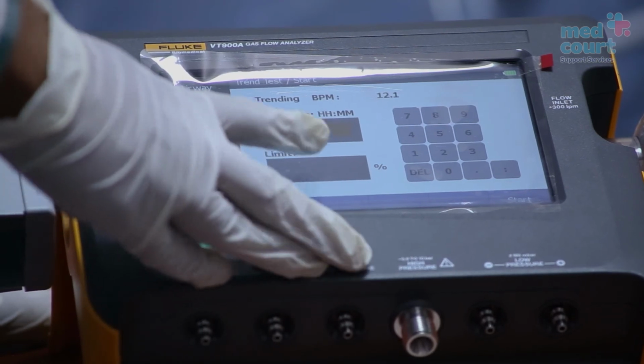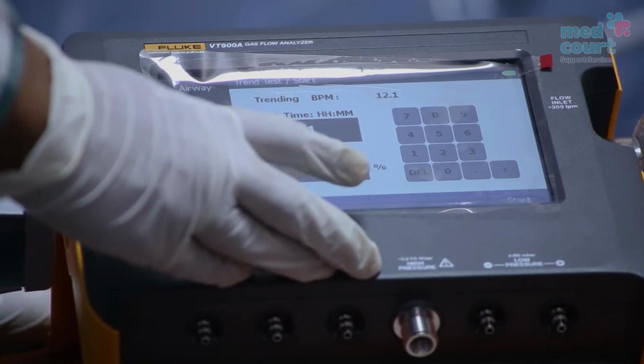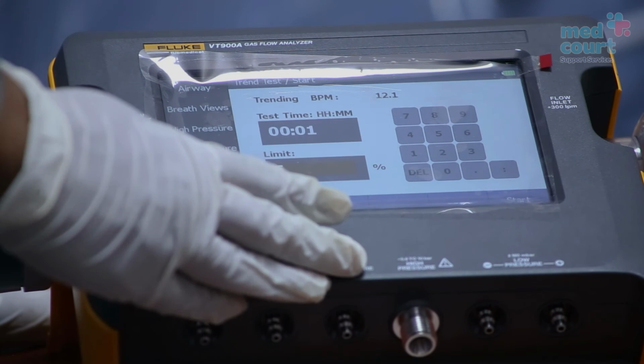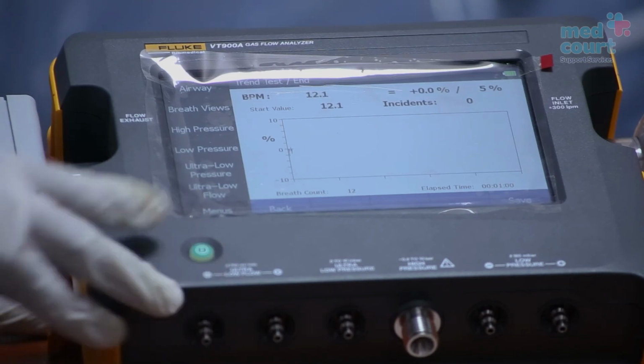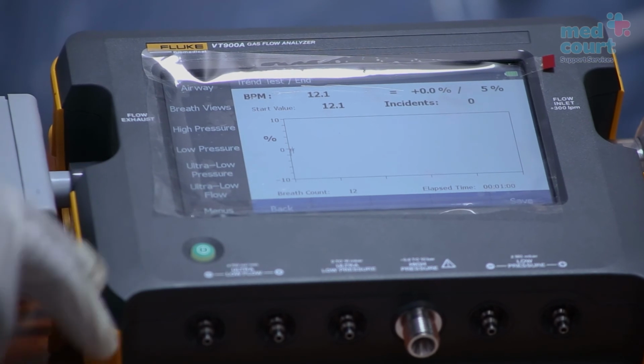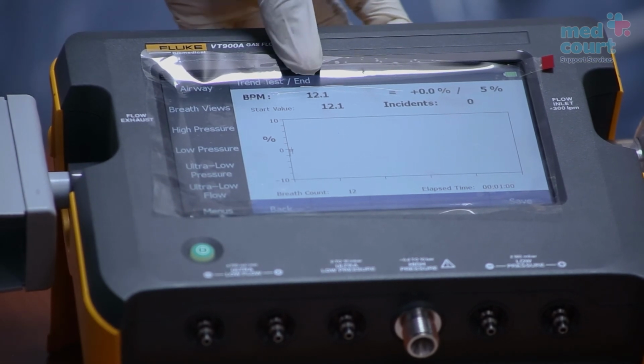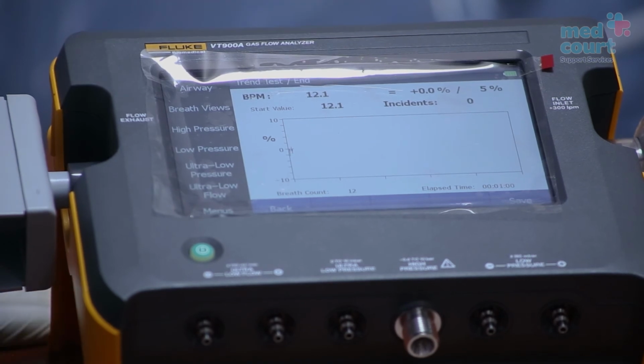We will be using 1 minute and a limit of 5%. Click Start. Once this has been completed, compare the results, which we have 12.1 breaths per minute, to what was set on the ventilator, which is 12 breaths per minute. Click Save.